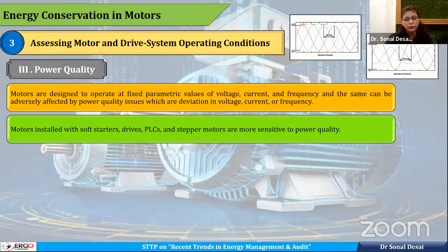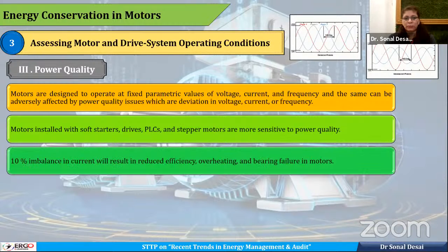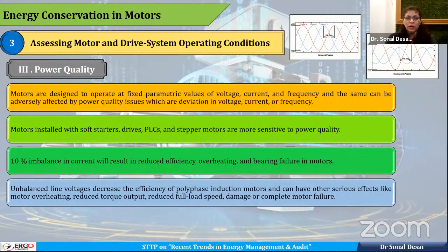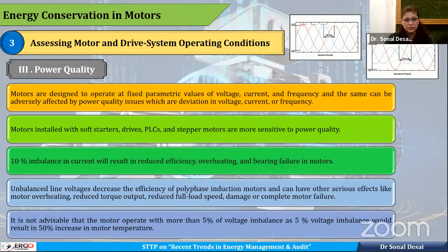More than 10% imbalance will create efficiency reduction, overheating, and bearing failure. So unbalanced line voltage decreases the efficiency of an induction motor, and it can have serious effects like overheating, reduced torque availability, reduced full load performance, and damage or complete motor failure. So it's not advisable that more than 5% voltage imbalance should take place in any motor operating condition.